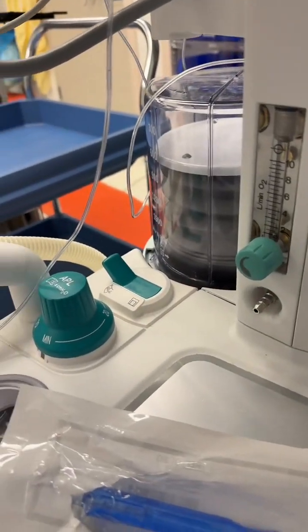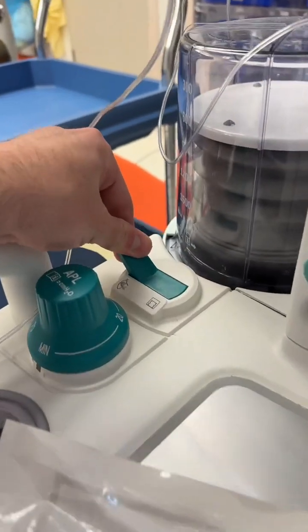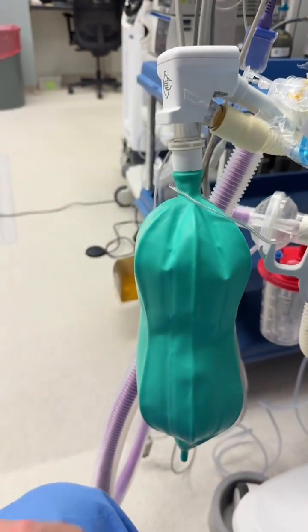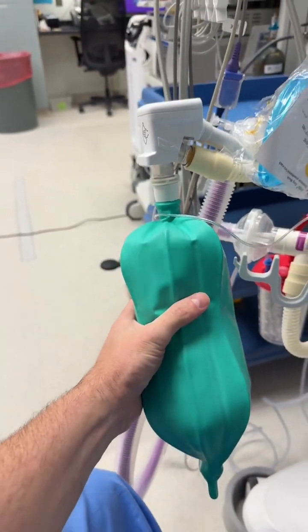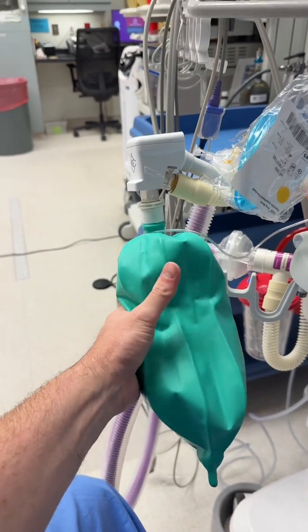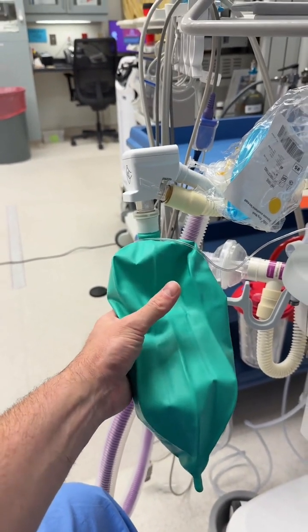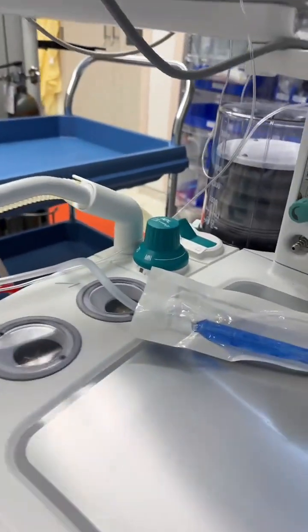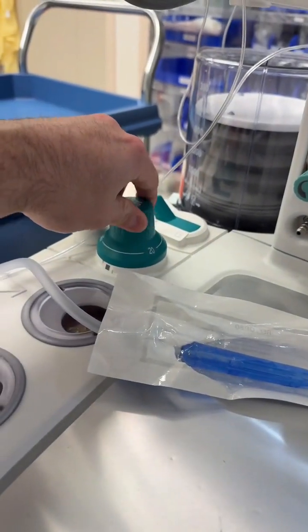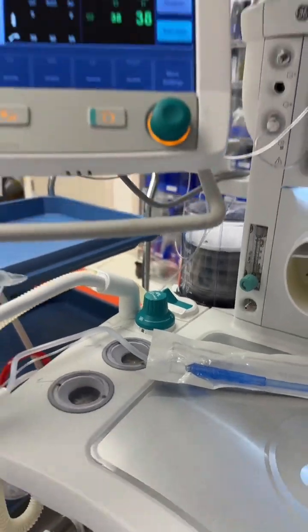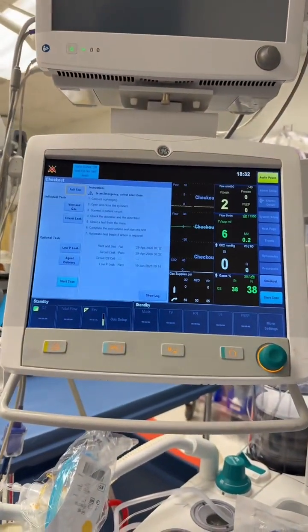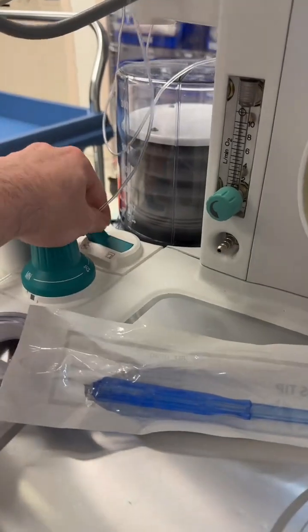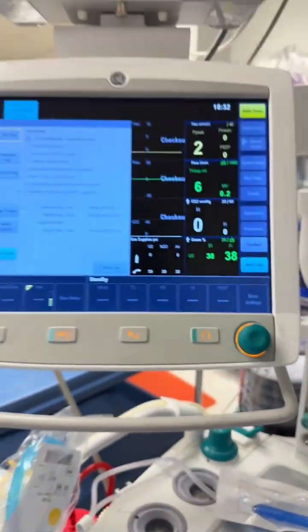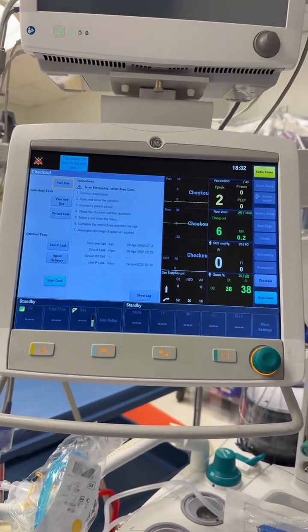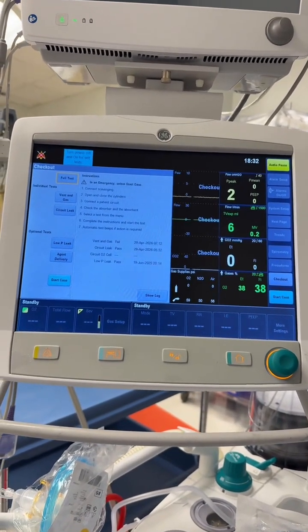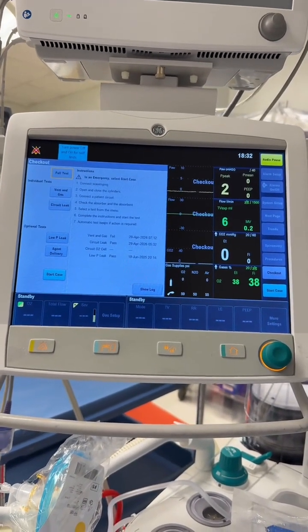There's a switch back here, and when we have it thrown over here, this means that this green bag is engaged and working, and we can manually breathe for you by squeezing this bag, and we can adjust the pressure inside the breathing circuit with this valve right here called the APL valve. Now, if we want to turn on the ventilator and have it do the breathing for you, all we got to do is throw this switch right there, and now the ventilator is on, and there's a ton of fancy settings on how we can program this ventilator to breathe for you.